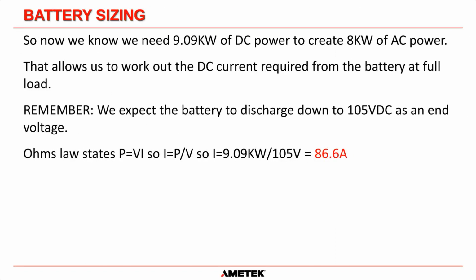That allows us to work out the DC current required from the battery at full load. Now, remember, this is very, very important. We do expect the battery to discharge down to a voltage of 105 volts DC. That is the end of discharge voltage. As current is inversely proportional to voltage when it comes to power, we have to make sure we use that value, because more current is going to be needed to give the same amount of power at this lower voltage. So Ohm's law states that P is equal to VI. So therefore the current is equal to the power divided by the voltage. So the current is equal to the power, which is 9.09 kilowatts, divided by that end of discharge voltage, 105 volts. And that comes out with, worst case scenario, we will need 86.6 amps of DC power to maintain that 8 kilowatt load. Okay.